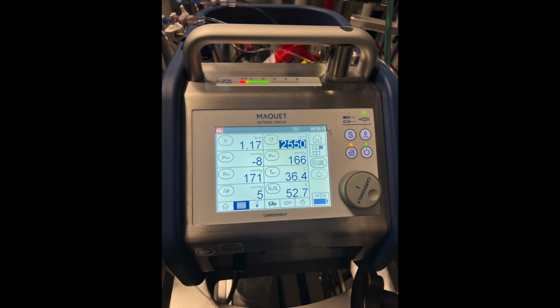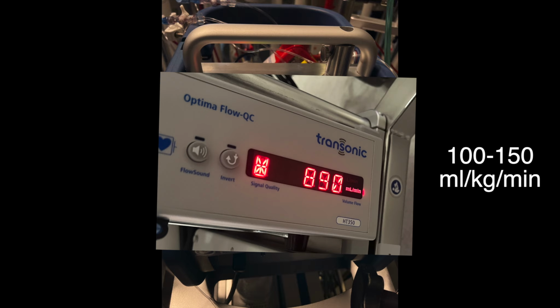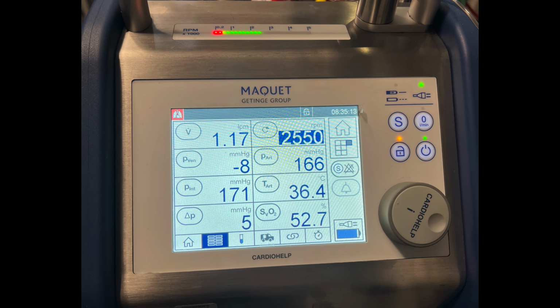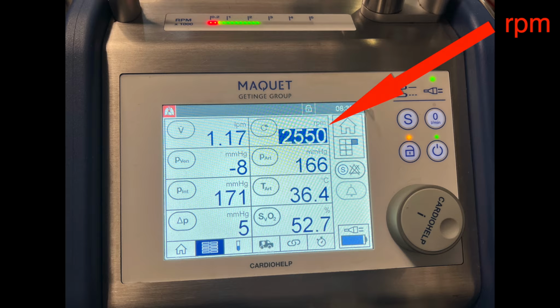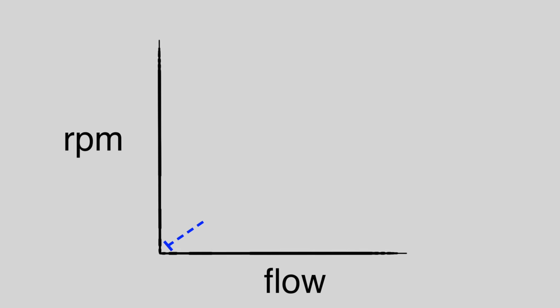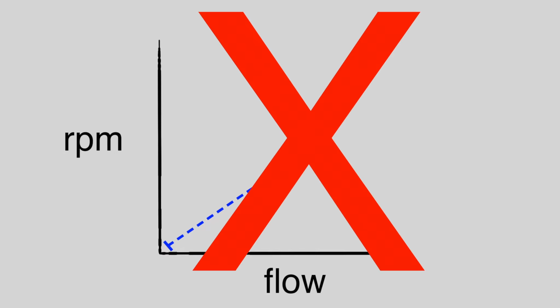The goal of the pump is to achieve adequate output, usually somewhere around 100 to 150 milliliters per kilo per minute for children. But we can't dial that number in. We can only tell the pump how fast to spin in RPMs. And a set amount of RPMs will not get you a set amount of flow, because those things are not in a linear relationship. This is because, like the heart, the pump is sensitive to both preload and afterload.